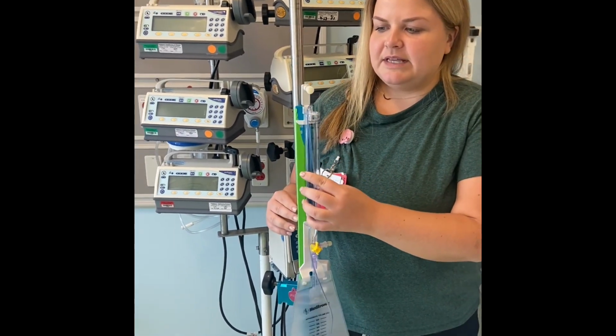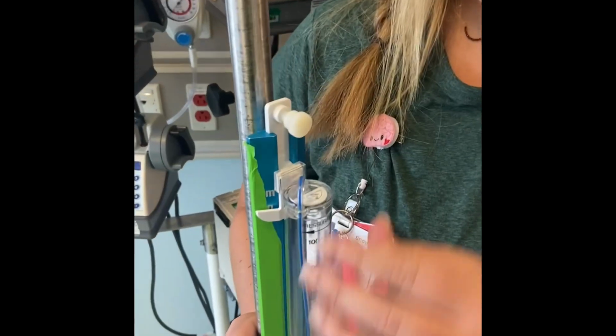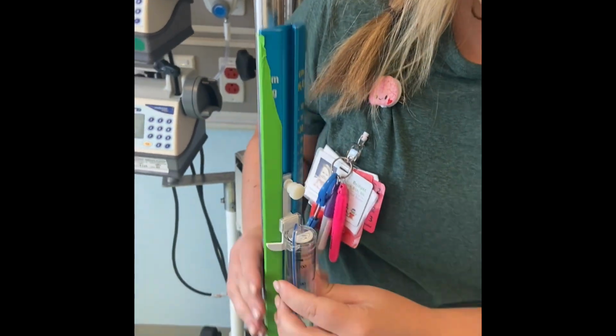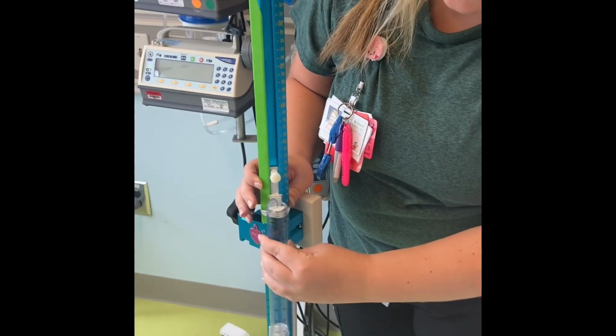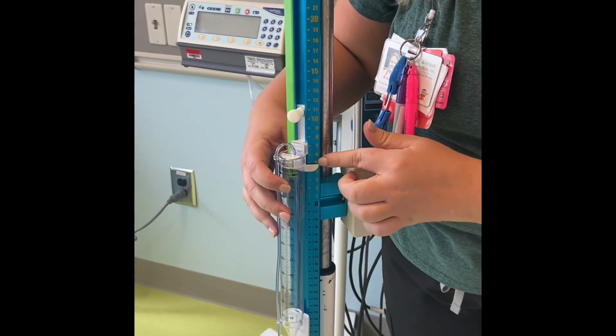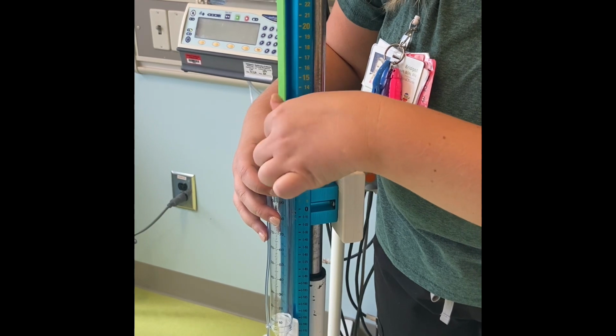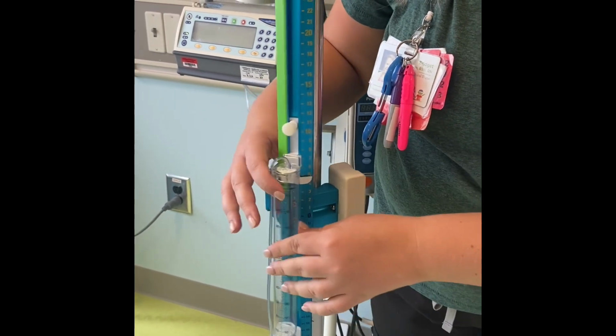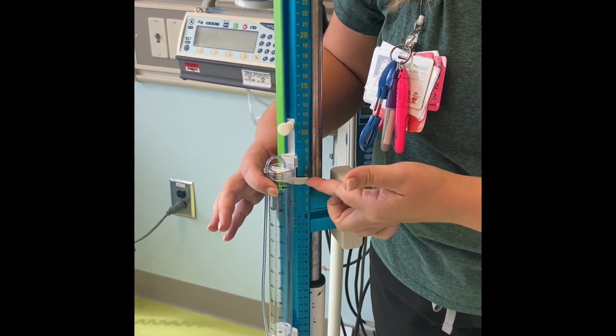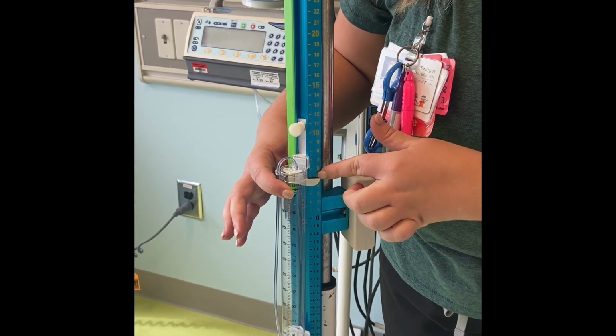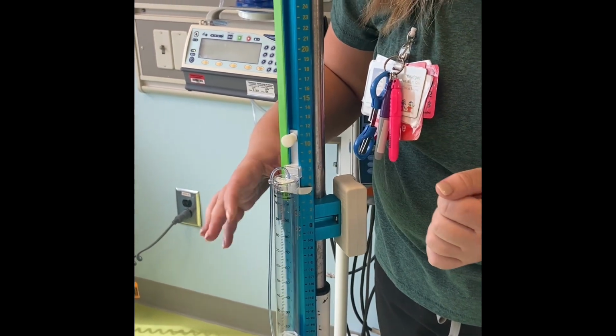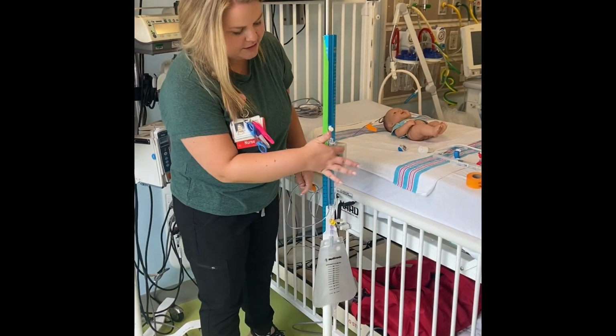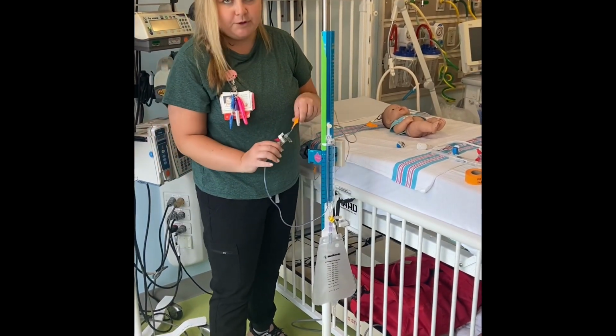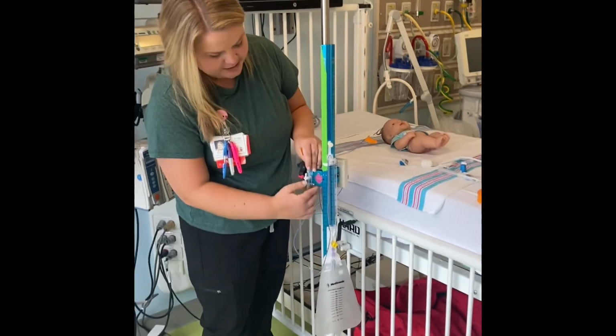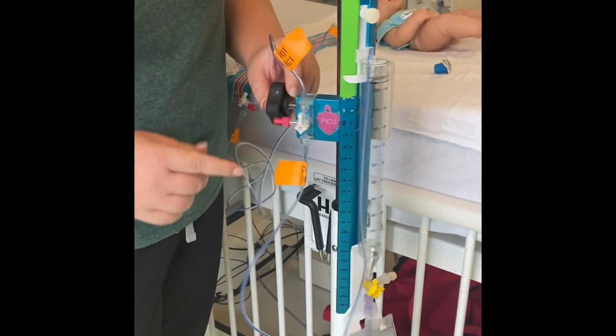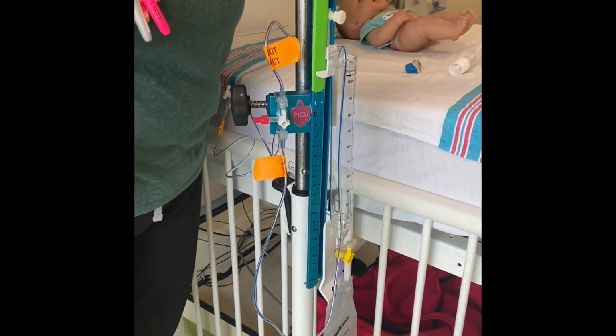You're then going to sit this inside your leveler, and you're going to bring this down until the flange is sitting at 5 right here, and then screw that into place. So you want to make sure that this portion of the EVD is sitting at the level 5, not this portion up here. So once you're at the correct level, you're then going to take this portion of the EVD, pop this in here, and this is going to be where I'm going to connect my transducer.